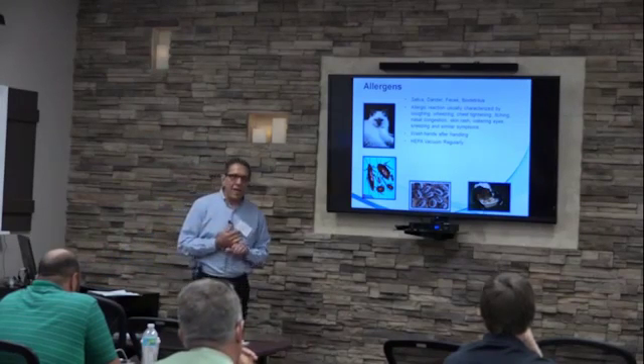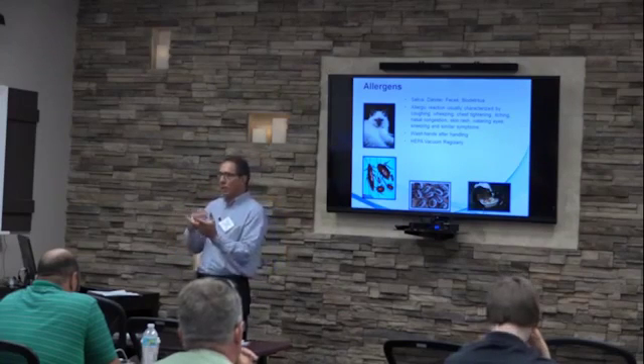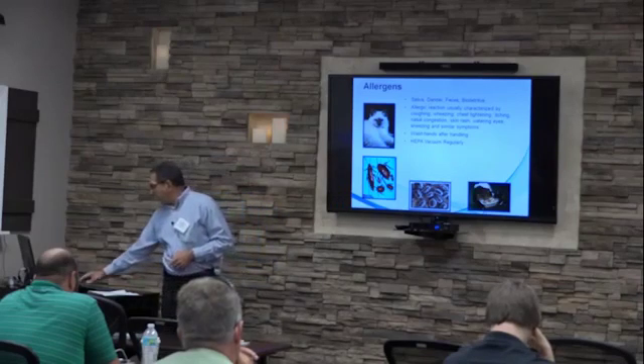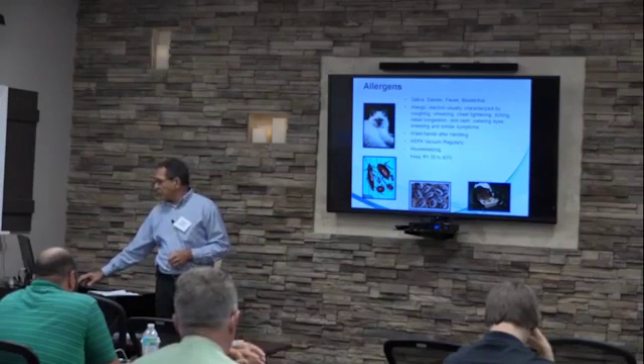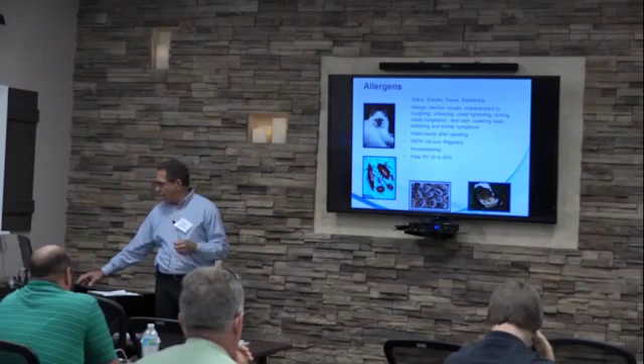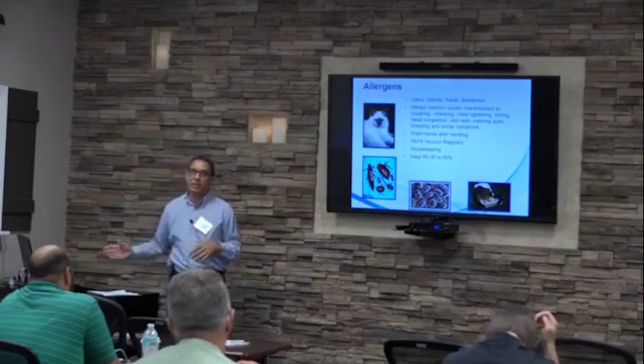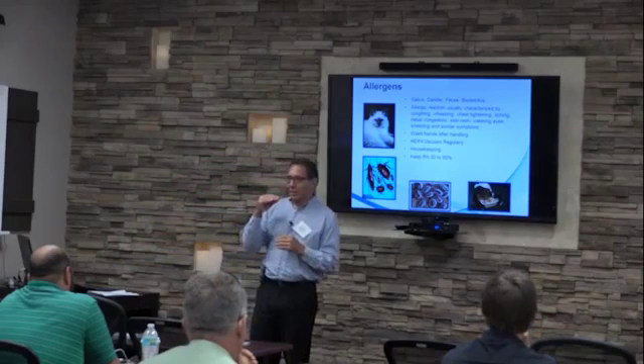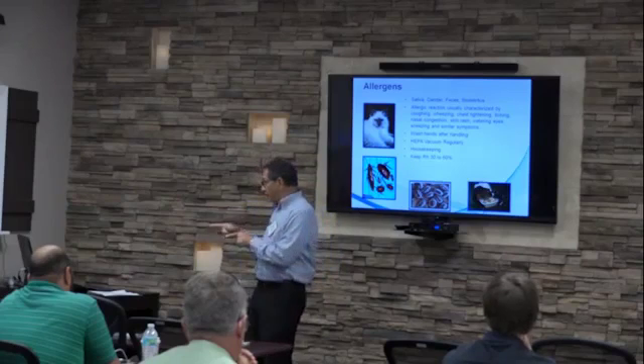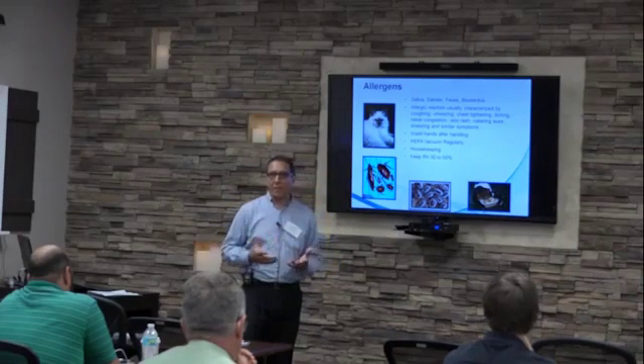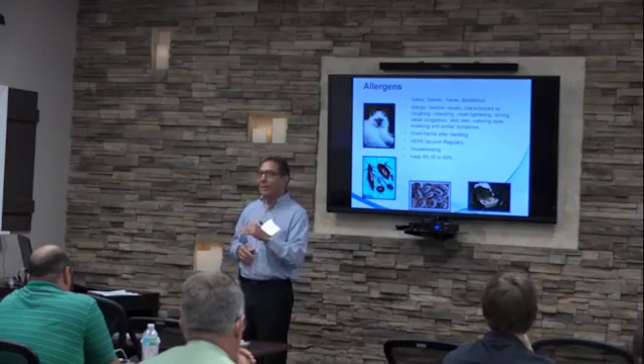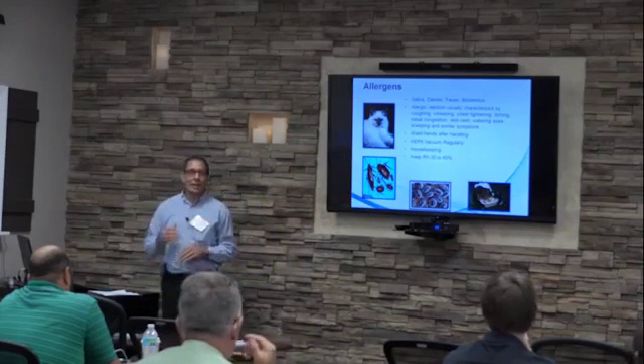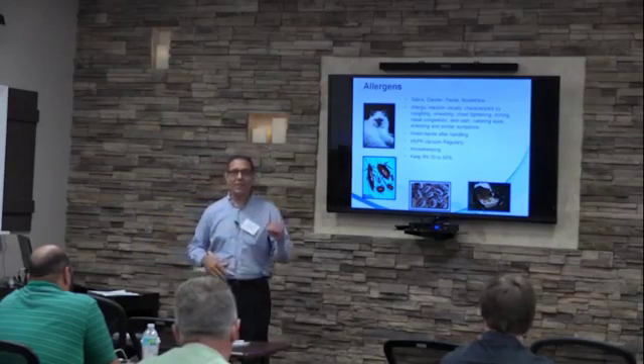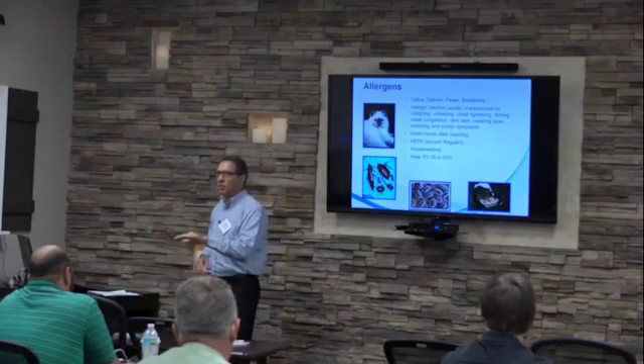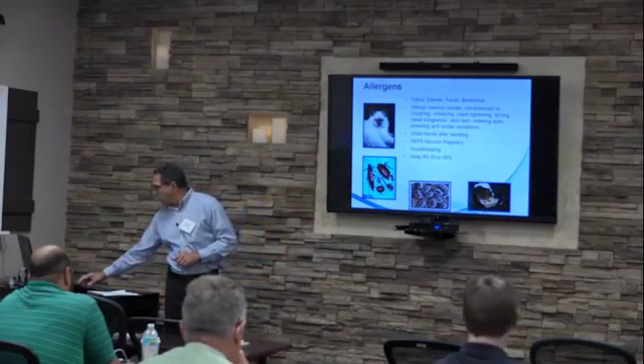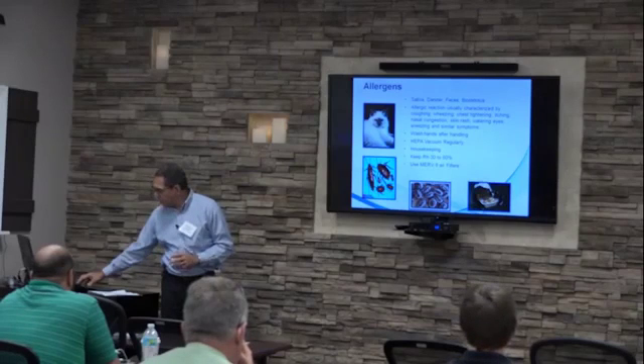We need to wash our hands when we deal with or handle these allergens. We need to use high-efficiency particulate air filters to clean these allergens out of the air. We need to make sure housekeeping is routine and done well. Keep the relative humidity between 30 and 60%. When relative humidity exceeds 60%, the prevalence of roaches and dust mites is going to be a lot higher. So maintaining relative humidity between 30 and 60% is one of the most important things we can do in a building, not necessarily for comfort, but to reduce the prevalence of these allergens.